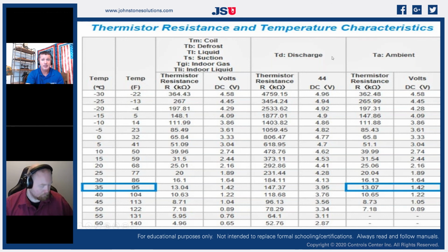The only one on these that is in a slightly different range is that discharge temperature thermistor, because it's on the discharge pipe. It's pretty hot, so it's got a different range value, but it's doing that same thing. If we're checking for DC voltage, it's the exact same way throughout our transducers and temperature sensors. So if I have, on a 95-degree day, a fault code that my outdoor temperature sensor is out of range, or it's open, or it's shorted or something, I can literally go unplug that temperature sensor, put my meter on resistance, and measure the resistance on it.